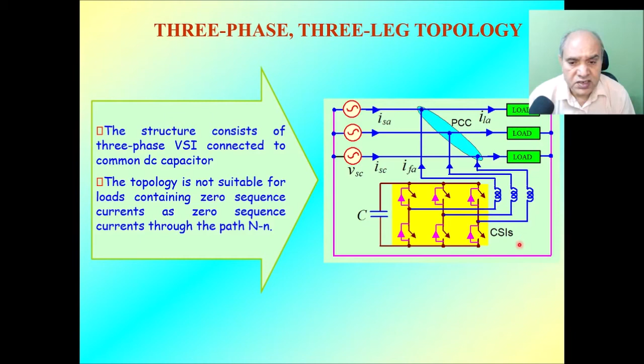To overcome this effect, we provide the neutral clamped inverter topology. Now, as the name indicates, there is a neutral which is clamped to the load neutral and the system neutral. So there are two DC storage capacitors, and the midpoint of these DC capacitors is connected to the neutral of the load and the neutral of the source.